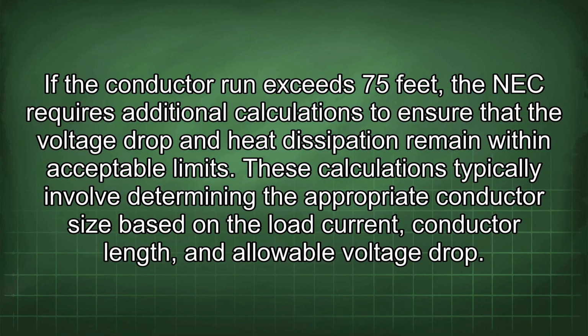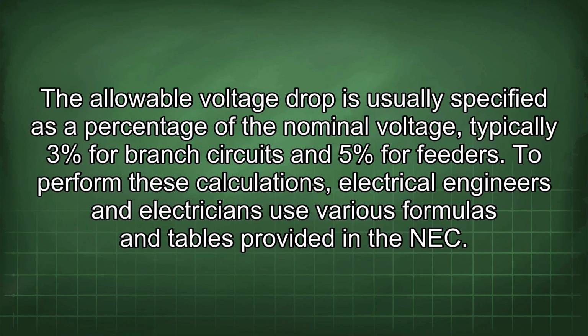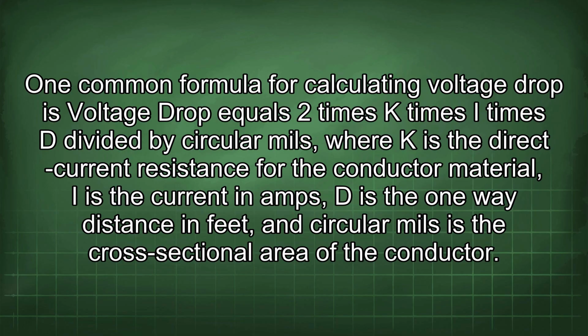These calculations typically involve determining the appropriate conductor size based on the load current, conductor length, and allowable voltage drop. The allowable voltage drop is usually specified as a percentage of the nominal voltage, typically 3% for branch circuits and 5% for feeders. To perform these calculations, electrical engineers and electricians use various formulas and tables provided in the NEC. One common formula for calculating voltage drop is voltage drop equals 2 times K times I times D divided by circular mils, where K is the direct current resistance for the conductor material, I is the current in amps, D is the one-way distance in feet, and circular mils is the cross-sectional area of the conductor.